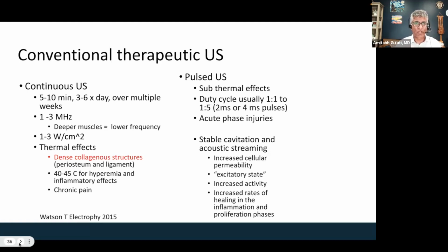You'll see that our megahertz tends to be 1 to 3 megahertz in frequency, so that the waves can get deeper and deeper through the soft tissue. And you'll see the acoustic intensities being 1 to 3 watts per centimeter squared. To put that in perspective, a diagnostic ultrasound may be 0.6 to 0.8 watt per centimeter squared. Dr. Gofeld's HIFU, you might be reaching in the hundreds or even thousands of watts per centimeter squared, depending on the technique and the acoustic intensity you're choosing. But our idea of therapeutic ultrasound is to have a hyperemic effect around 40 to 45 degrees centigrade.